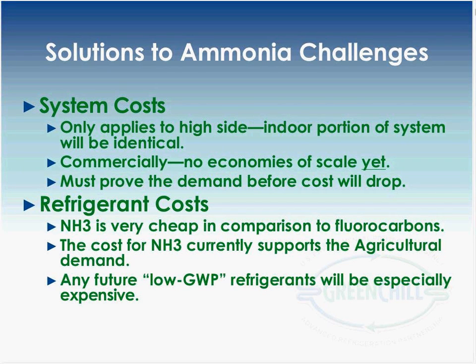This is probably one of the hurdles, just because there are no economies of scale yet with ammonia commercially. It's important to note it's only going to apply to the high side. Everything in the store using a secondary system, your pump skid, cases, and distribution piping inside, none of that's affected by using an ammonia system. Basically, you take a standard secondary HFC system and put the ammonia on the roof. So the cost that is greater is limited to just that high side of the system, and since there's no economies of scale yet, it's going to take proving the demand for manufacturers to really start putting them out.